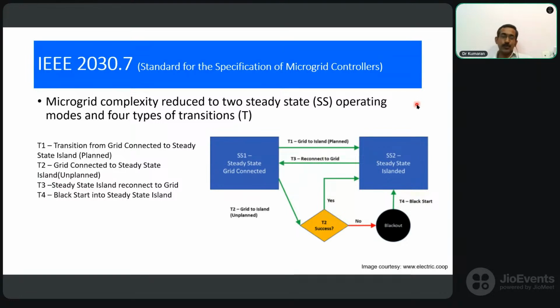The functions of the controllers, they are also the functions of microgrid controllers, and they are very specifically mentioned in one of the IEEE standards. For instance, IEEE 2030.7 specifically addresses microgrid controllers. If you read this standard, we can boil down the operations into simple arguments by splitting the steady state operating modes into two states, as illustrated beautifully in this image. And we can have four kinds of transitions.